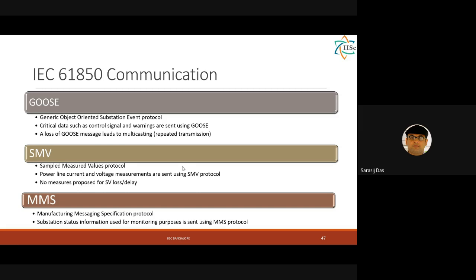GOOSE is nothing but a protocol to send trip and block information. The control signals are sent through GOOSE messages. All tripping signals should also be sent as a GOOSE message. And what will be the message structure? That is defined in this standard.